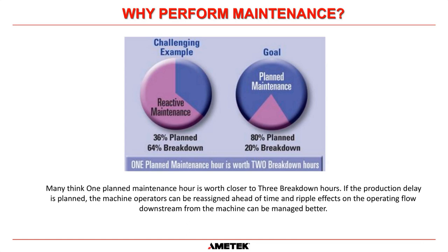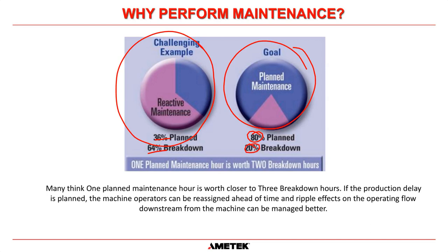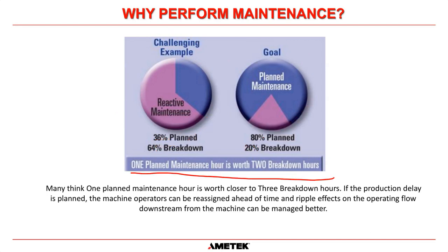This first example is a bad example where it's all reactive maintenance, basically. We're only doing 36% planned maintenance and 64% breakdown maintenance. And the goal is to get to 80% planned maintenance and therefore only 20% breakdown. Because this slide here says that one planned maintenance hour is worth two breakdown hours. A lot of people out there actually say one planned maintenance hour is worth three breakdown hours. Okay, because if the production delay is planned, then the machine operators can be reassigned ahead of time, and any ripple effects of the operating flow downstream from the machine can be managed better. So if everybody knows that the UPS is having maintenance performed on it, then if something does go wrong, everybody is in place to make sure we can get the loads back up and running again as necessary.